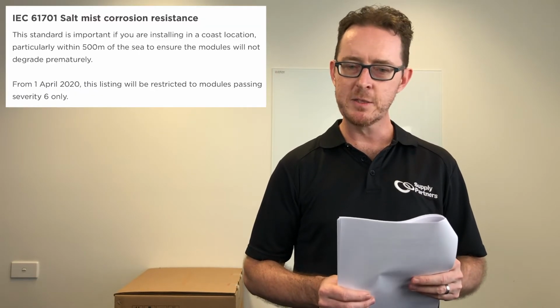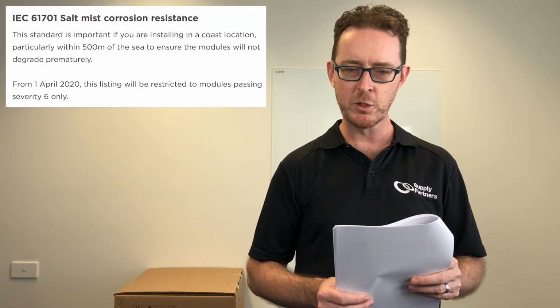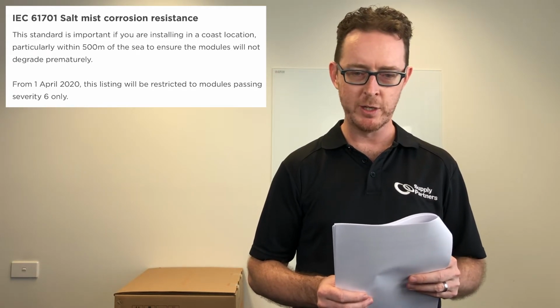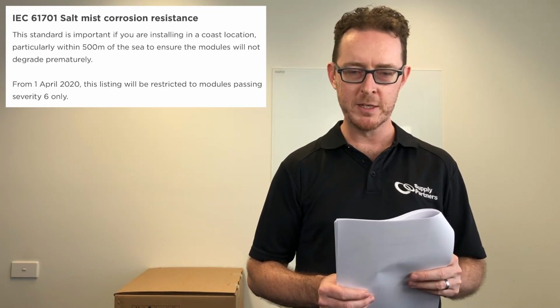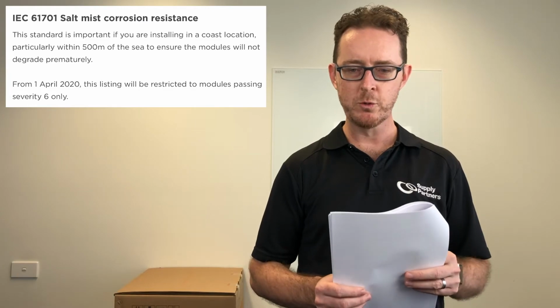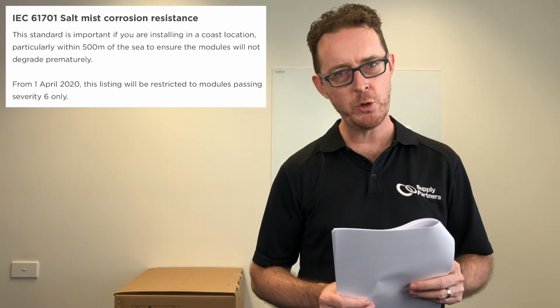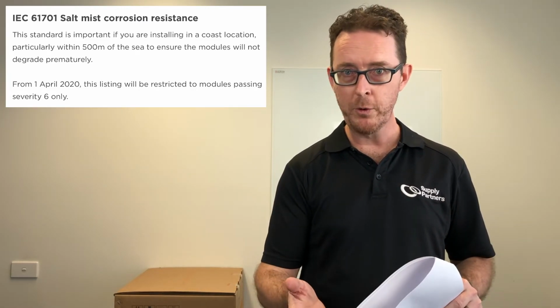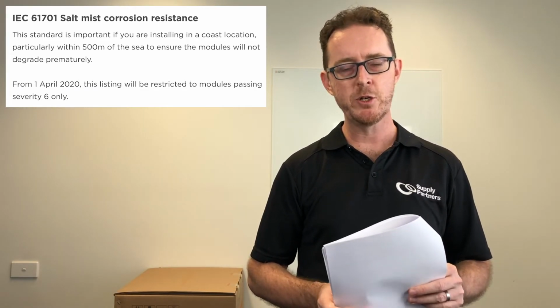Now, what's the relevance? The relevance is that the Clean Energy Council has an enhanced listing for PV module manufacturers that is related to salt mist testing. And they go on to say on their website, this standard is important if you are installing in a coastal location, particularly within 500 meters of the sea, to ensure the modules will not degrade prematurely, which is appropriate, which is valuable information for end users.